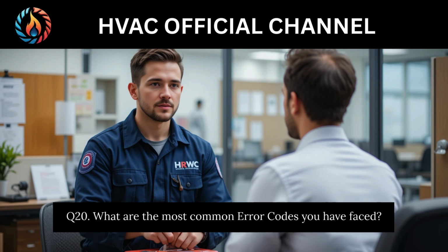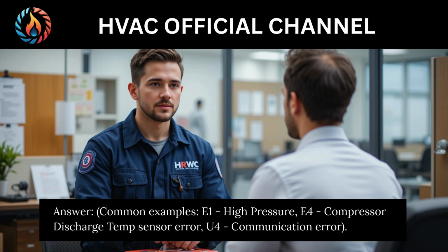Q20. What are the most common error codes you have faced? Answer. Common examples. E1, high pressure. E4, compressor discharge temp sensor error. U4, communication error.